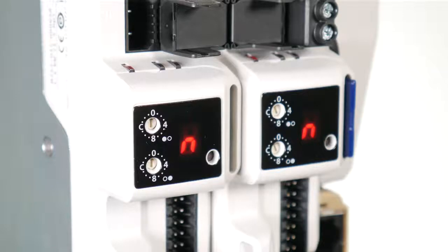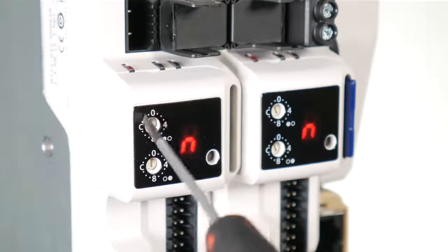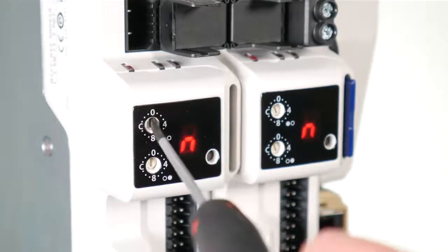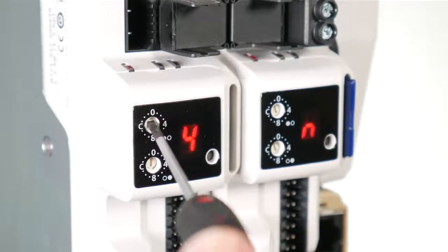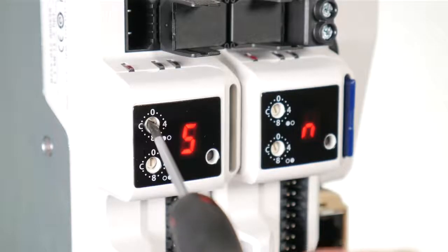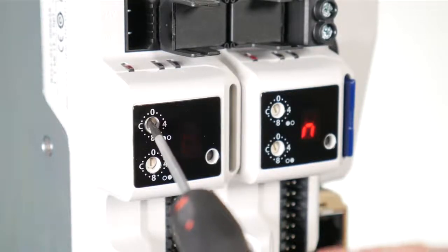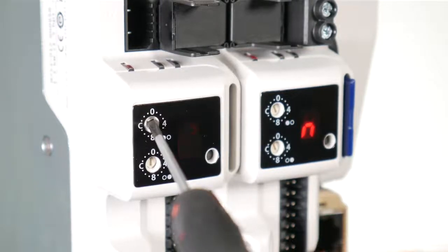Once the dials are set to the desired configurations, the display will confirm the dial settings in hexadecimal, followed by the actual station alias or node address setting in decimal. The dial settings and station alias or node address settings are separated with a hyphen. Once the desired dial configurations have been set, the KI compact display will transfer the value to parameter 11017 keypad defined node address.